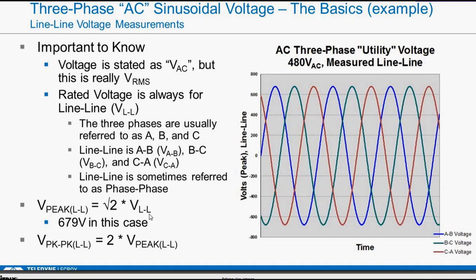The peak voltage now, if you follow through, is a little bit different calculation because it's a line-to-line voltage. The peak voltage is square root of 2 times the line-to-line voltage rating, or in this case, square root of 2 times 480 volts AC. If that was a 400-volt system, you'd be in the high 500 volts for that peak voltage. And then the peak-to-peak voltage is 2 times that, or almost 1400 volts in this case.